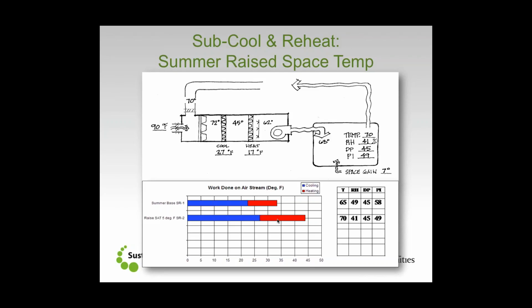So if we're talking about changing set point conditions in spaces, we have to think very, very carefully about whether we're simply changing the space set point temperature or whether we're telling the system to do something entirely different when it comes to the dehumidification aspect of operation.